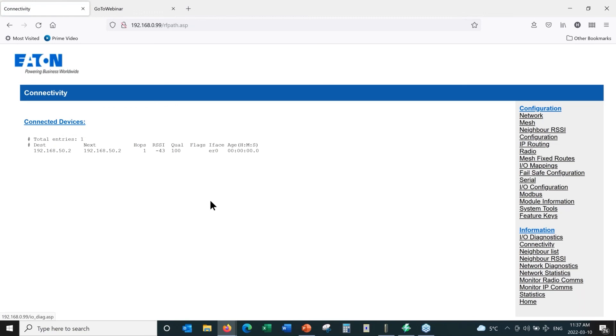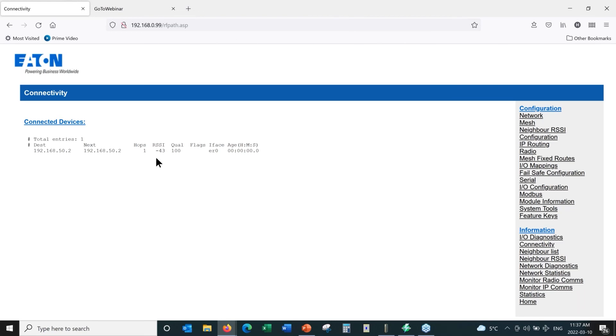The next screen is the Connectivity Screen, which we use a lot. It tells us we have one remote radio that this base radio can see. It is only one hop away, meaning a direct connection. If the radio were going through repeaters, we would see two or three hops. This shows the received signal strength indication — probably one of the most important parameters we look at for these radios. The quality value of 100 indicates that no error correction has been required and the radio has not had to do any retries to get messages across.